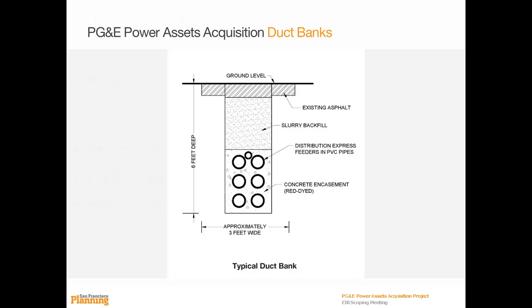This figure shows an example of an underground duct bank. Work within the Martin substation, as well as distribution system separation work on city streets, could utilize underground duct banks to protect and route electrical cables between connections with electrical equipment or structures. As shown in this figure, cables would typically be located within PVC pipes and encased in concrete in an underground trench. The proposed distribution express feeders would be constructed in a similar manner.